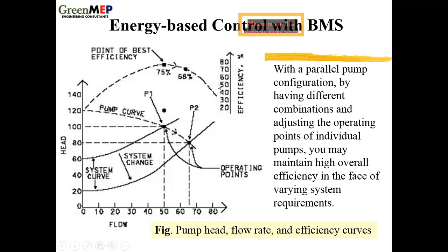But if you operate off this point, off design, somewhere here, 50%. 50% means 50% of the electricity you supply to your pump is wasted inside the pump. You cannot achieve the 80% saving that we are talking about. You have to do maximum and try to stay here. This is the operating point, right? This is the pump curve, pump flow. When the flow increases, pressure capability drops. This is the system curve. Right? The system curve shifts depending on the load. When the valve is open in the chilled water circuit, for example, the head changes, the system curve changes. You're operating here, efficiency 75%. When the system curve changes, this is your new operating point, and your efficiency will be much, much lower.